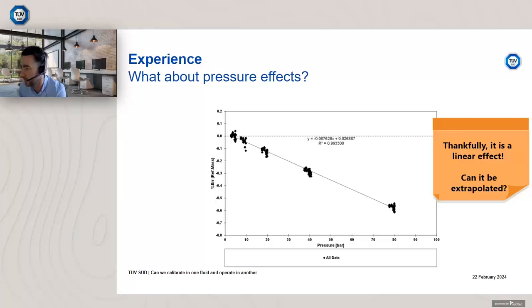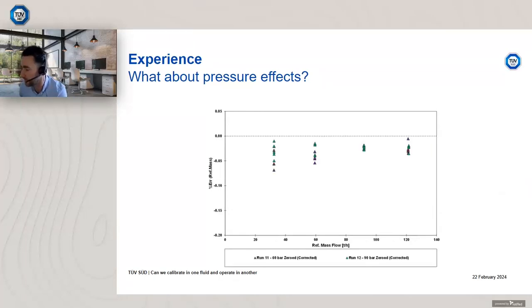We've only calibrated this up to 80 bar, but there's applications where people are using up to 200 bar potentially. Thankfully, this facility can operate up to 100 bar, so I derived this pressure correction with this set of data and then operated it at different pressures. So the next set of data I show you, I have 60 bar and 90 bar, which you can see we didn't calibrate the device at to derive the correction, but then calibrated it afterwards.